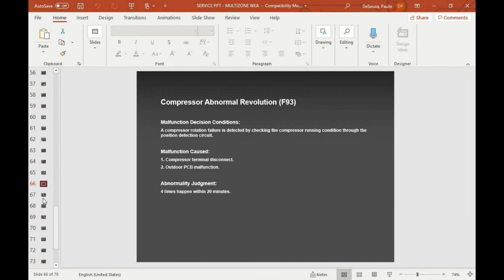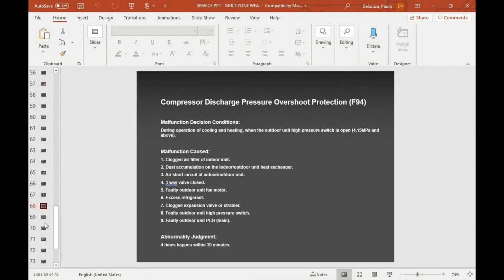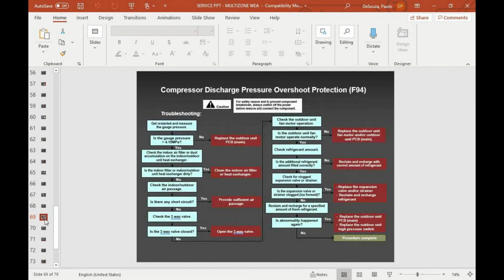So this is what happens in the long run, and especially on a colder day or on a very high humid day, you have this problem. So please, when you get to see this kind of picture at your job site, recover the refrigerant and check for leaks. If no leaks, recharge. And if you tell me, how come I got lack of refrigerant, less gas, and Paul, I can't find any leak, chances are you ran away with refrigerant with your gauges, or maybe you pressurized the system with nitrogen over 500 and caused this problem, or maybe the system came from the factory with low refrigerant. Okay, I'm not blaming you all the time. I can take that blame as well.